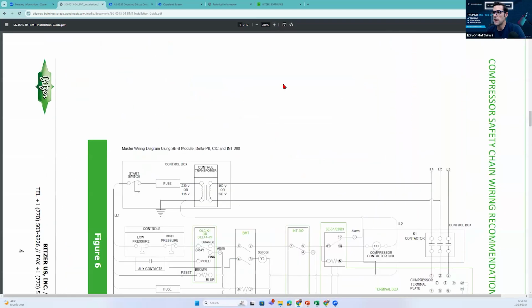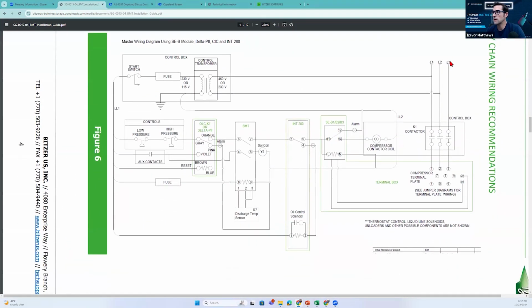And the way it works, you always want to get into the manuals and dive in and look at how it works. So here's our L1, L2, L3. This is our power coming in. We've got the control box, so it's showing a transformer here, but here are the controls: low pressure, high pressure control. You've got your OLC, that's your optical sensor, or your Delta-PII. This is your pressure sensor. Doesn't matter which one it is.